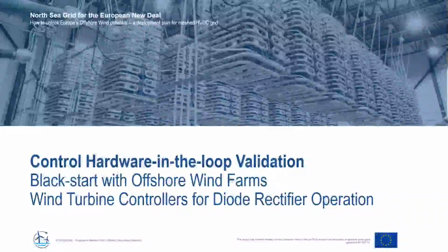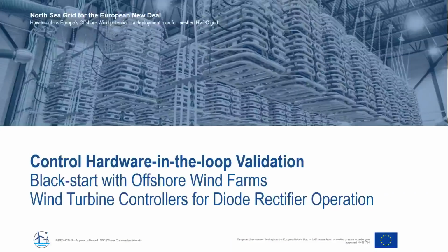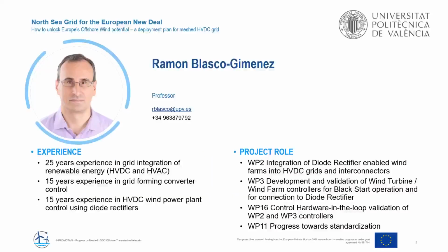Our next presentation deals with the control hardware in the loop validation of grid-forming wind turbine controllers, first for black start operation with offshore wind farms, and second for the connection of offshore wind farms to diode rectifier HVDC links. My name is Ramon Blasco-Gimenez, and I'm a professor with the Technical University of Valencia in Spain. We've been working for about 15 years on wind turbine grid forming control for both HVDC and HVAC integration. Within the promotion project, we've been working in 4 work packages on the development and validation of wind turbine grid forming controllers for diode rectifier connected wind farms, and also for black start and islanding operation.